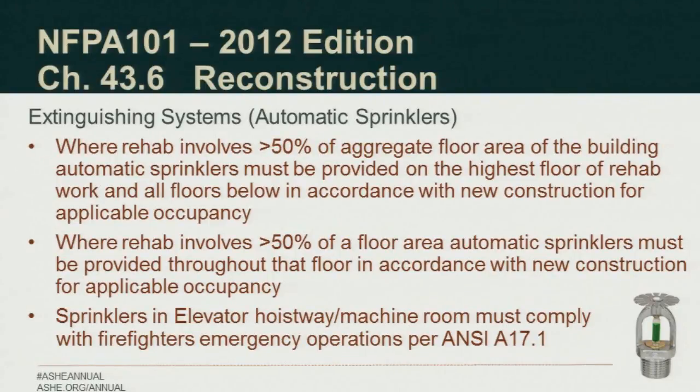Question for you on the last one. Sprinklers in elevator hoistways and machinery rooms. Does that meet with the elevator code? You might have more than one fire marshal and elevator code inspector who knows the code. So what this is saying is that if one of these sprinkler projects that gets triggered results in sprinklers being installed in an elevator hoistway or machine room, you must meet the requirements of firefighter emergency operations as required by A17.1, which is new construction. So phase 1 recall and phase 2 firefighter operations would be required for the elevator.